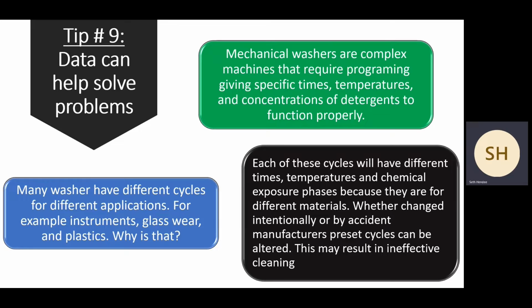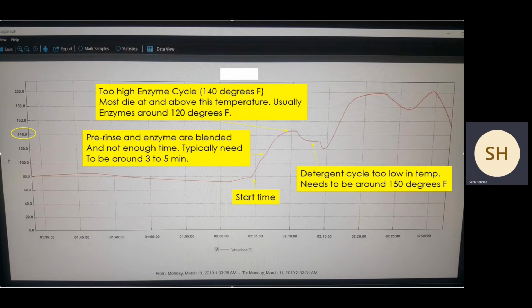So this may result in ineffective cleaning, right? Sometimes people will say, I took a minute off the dry time, or I mean, you name it, right? Because to shave a minute doesn't seem like a lot for an individual cycle, but then if you're a 24/7 department, somebody thinks that they're saving minutes to hours a day in their cycles, but it causes problems. Now, there are ways to plot cycles. You can put devices in a washer and let it go through, and it will look at times and temps. So there's a few things here to look at, and you get better at reading these plots the more practice you have. Here are some problems we see on this one.